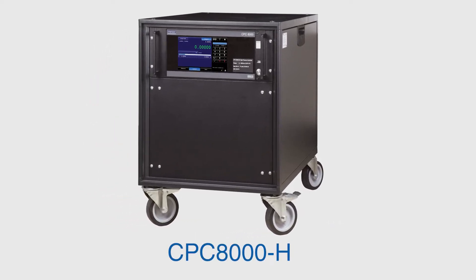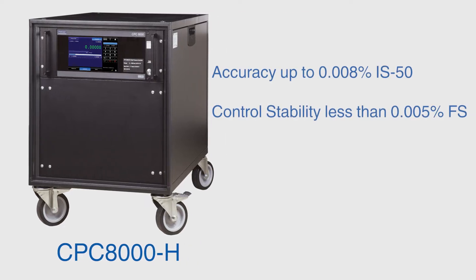In this video, we will set up and perform a three-point calibration with a hydraulic pressure controller. For this calibration, we will use Mensor's CPC8000-H hydraulic pressure controller at zero, midpoint and full scale. The accuracy and control stability of the CPC-8000H is optimal for calibrating, testing and characterizing industrial pressure sensors.